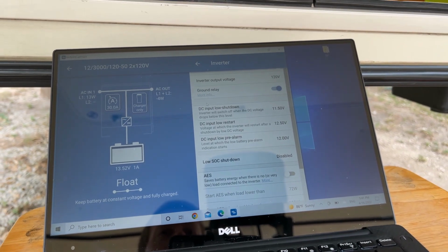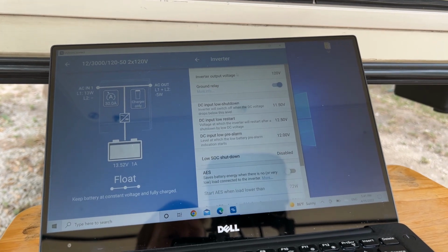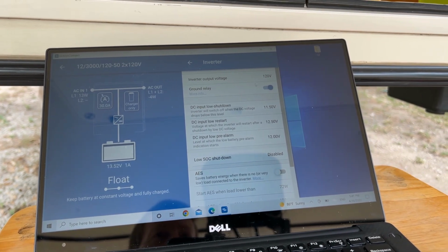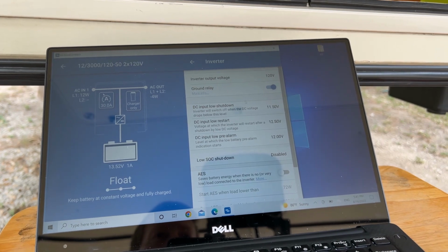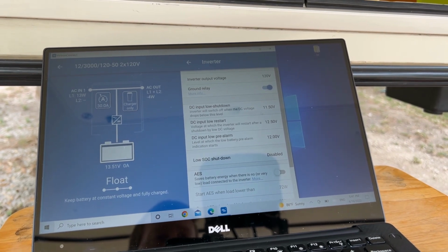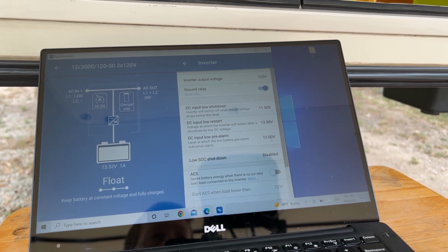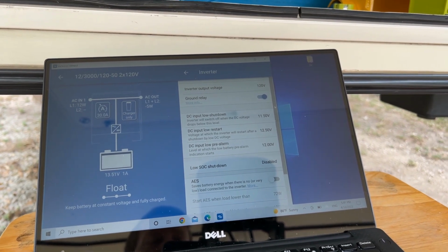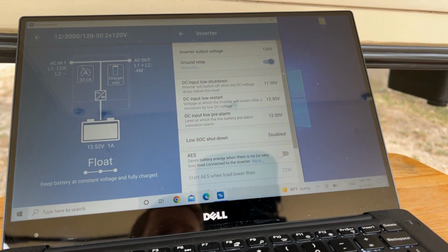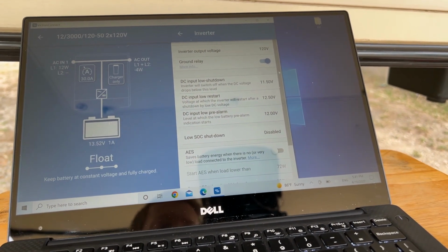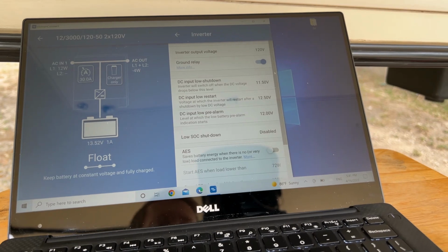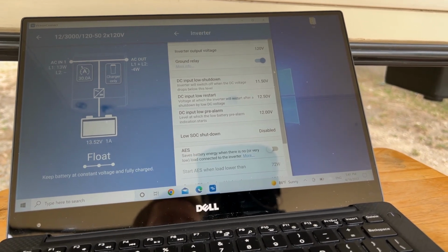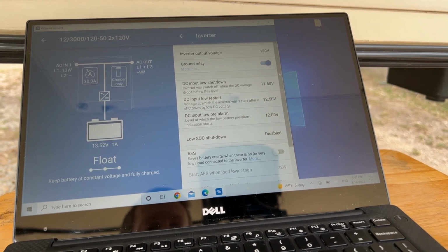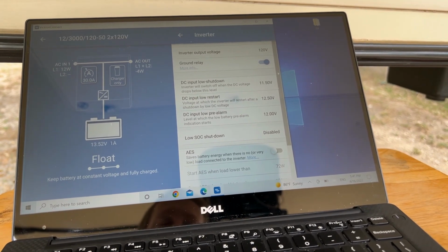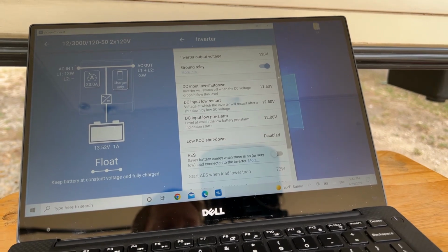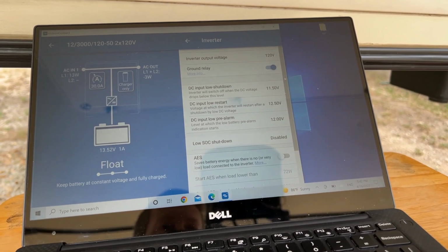Finally, we've got the inverter settings here. Again, it's set to output 120 volts. We're in North America, obviously. There are some ground relay settings, things like that. It's got some input voltage cutouts, which are most important for your battery. If your battery's BMS cuts out at 11.3 or 11.4 volts, you might want to set it a little bit above that so that your batteries don't have to go into their own protection mode. You can have the inverter shut off prior to the batteries and their BMS activating to shut down. So that's what I've done here.